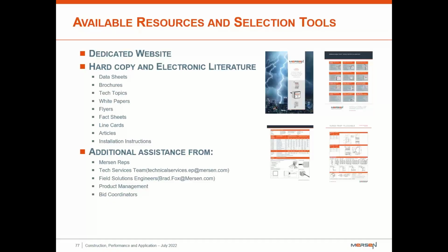The whole fuse coordination panel, which has fuses in it, was designed to be put into buildings for safety features. After the planes crashed into the towers, the lights inside of the stairwells went out, and so they came up with this fuse coordination panel that will actually protect branch circuits and raise their interrupting current up to 200,000 amps. Bussmann came out with a cube fuse because they wanted to corner the market, which is a very good design in what it is. When COVID happened, which none of us actually saw coming, 3M stopped making the resin that they used for those. Now, you couldn't take a Littelfuse product or a Mersen product and slap it into those panels. You had to have this proprietary fuse that would actually clip in there. And they couldn't produce it because they weren't even getting the resin. And they went to like 52 weeks lead time, and these things are used for schools and hospitals and things like that.